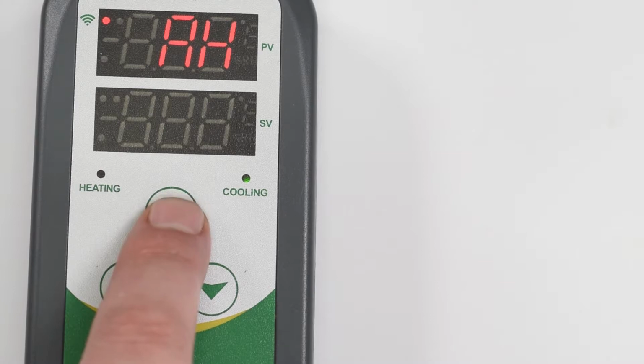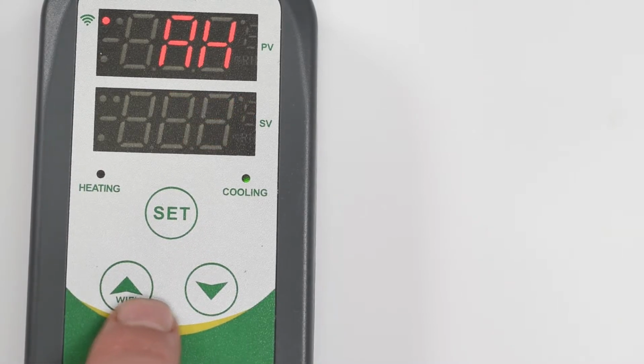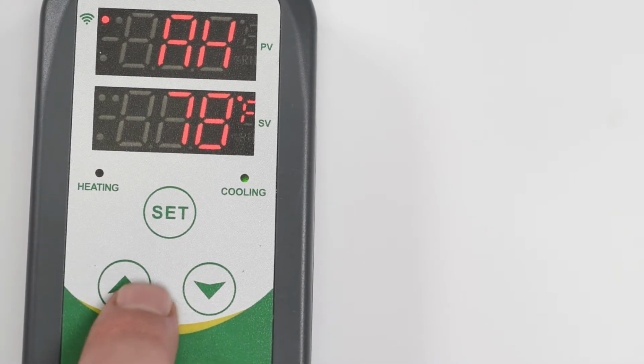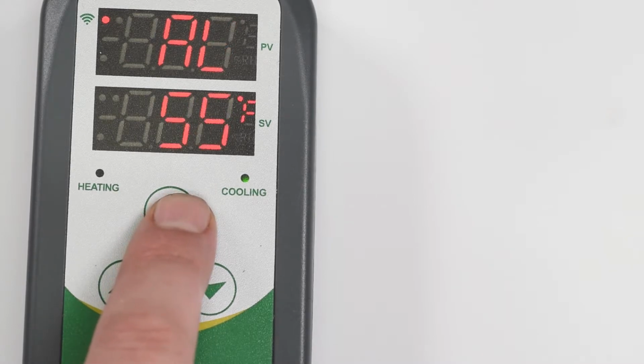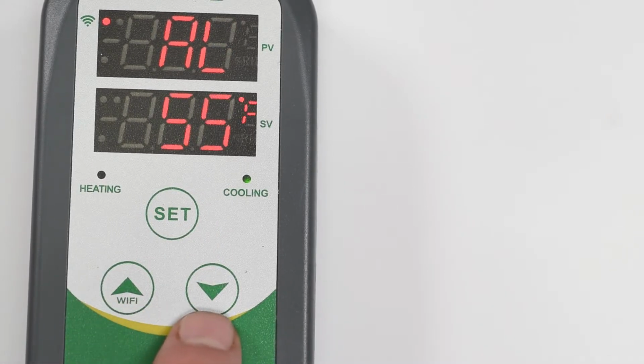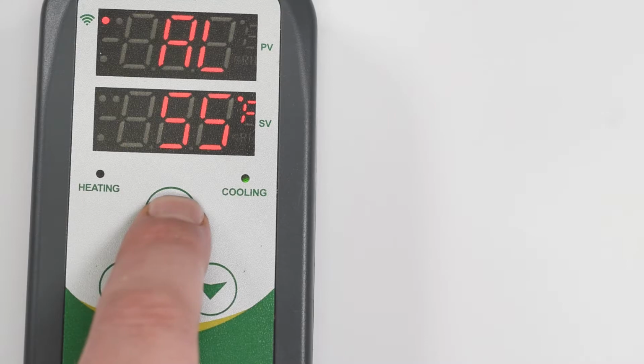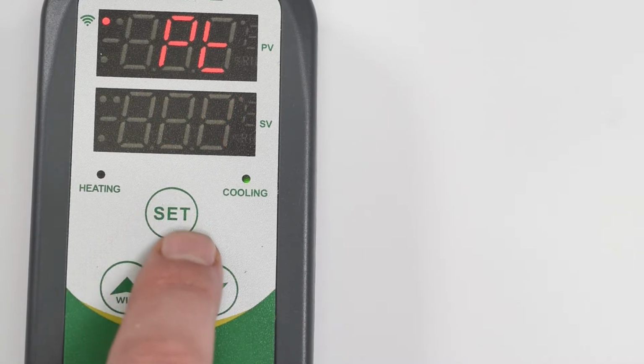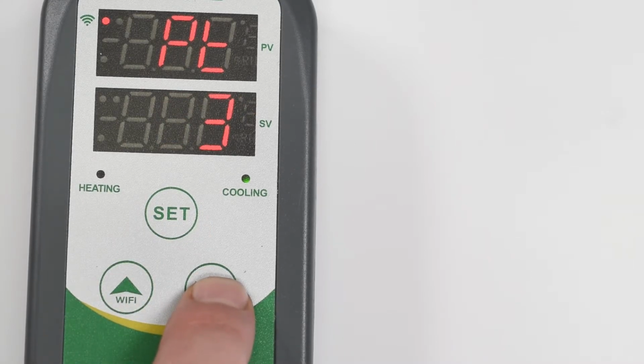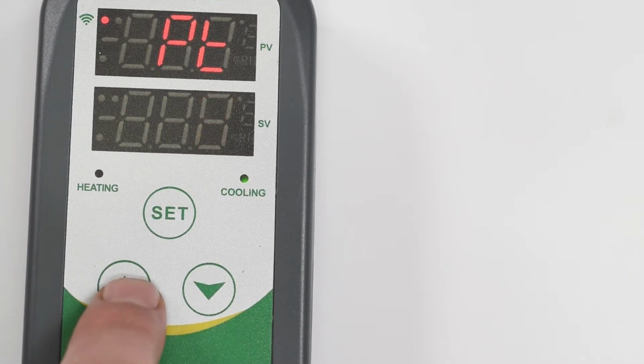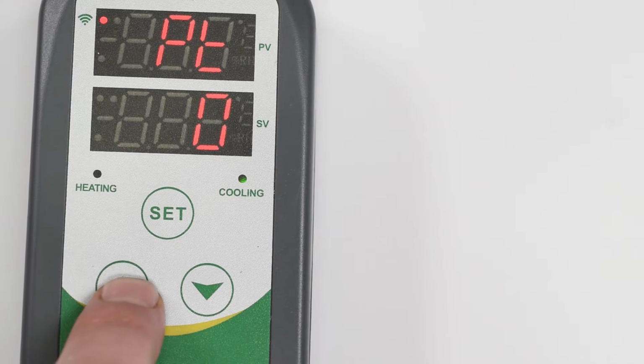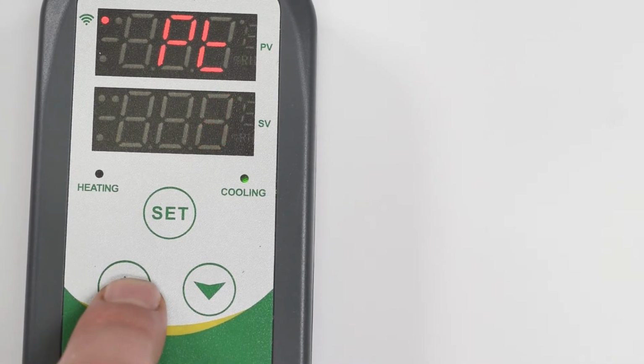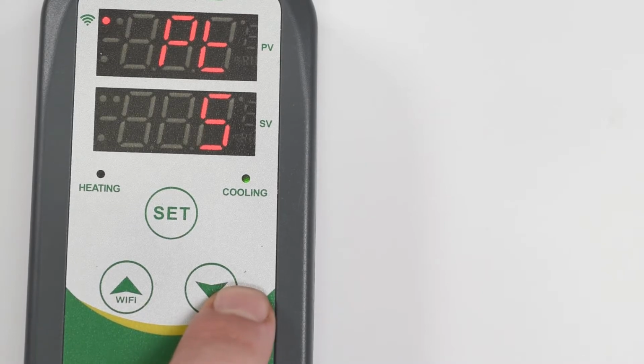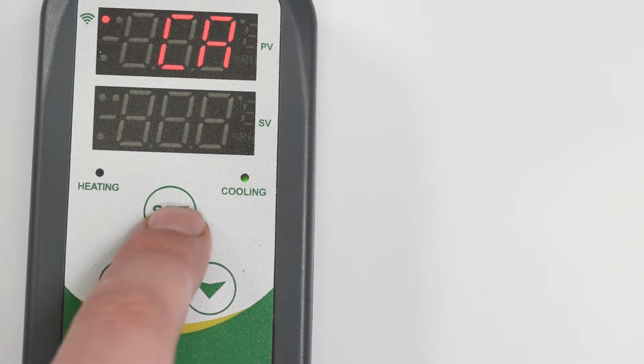Press set yet again and you get alarm high. This should be how hot things are allowed to get before you want to be alerted that something might be wrong. Up next is AL, and that's the same thing for low. Up next is PT, and that stands for compressor delay time. Clearly, this is how many minutes in between turning on the cooling device has to pass before it will turn back on again. Check the user manual of whatever you're using to cool just to make sure, or set it to at least 5 or longer.